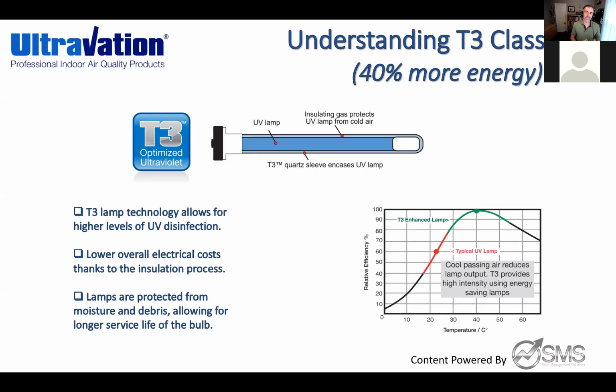What people don't realize is that the average UVC wavelength bulb should be changed on a PM cycle annually. Our UVC wavelength bulb, we make it very clear, is a 9,000 hour bulb. Can it stay lit up for months to come? Absolutely. We sell our bulbs, whether it's 1 year or 2 year life T3 class, with a 2 year warranty. The warranty, which most manufacturers should clarify, just means the bulb will light up for 2 years. But are you getting the disinfection rate and the intensity? No.